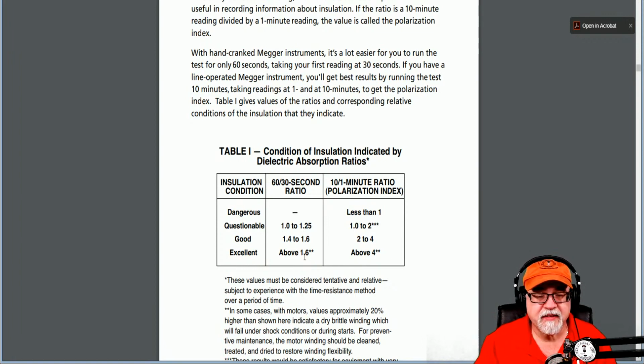And if you do a 10 and 1, it means I take the value that I got at the 1 minute, and then I take the value I got at the 10 minutes, and I divide the 10 into 1, okay? That's going to give me what's called a polarization index. And again, if it's 1.0 or greater for wire and cable, then I'm telling you it's probably okay. Then you would just consult with your manufacturer. So ideally, we'd like to see 2 or greater in the polarization index, and we'd like to see at least 1.4 or greater in the 30 to 60 second absorption test. That does not mean that 1.0 is bad when it comes to wire and cable.